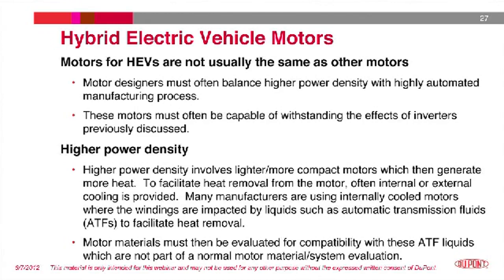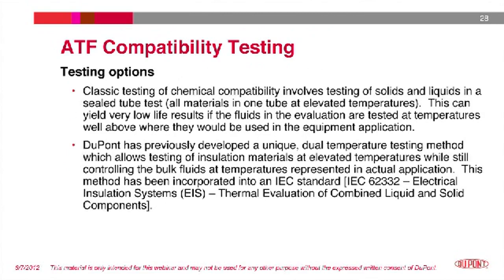One way to increase the power density is to improve the heat removal from the motor by using internal or external cooling. For internally cooled motors, fluids such as automatic transmission fluids are sprayed on the motor windings to remove the heat more efficiently. However, motor materials must then be evaluated for chemical compatibility versus these types of fluids, which are not used in typical low voltage motors. Classic testing of chemical compatibility involves testing of solids and liquids in a sealed tube test, where all of the materials in one tube are at elevated temperatures.